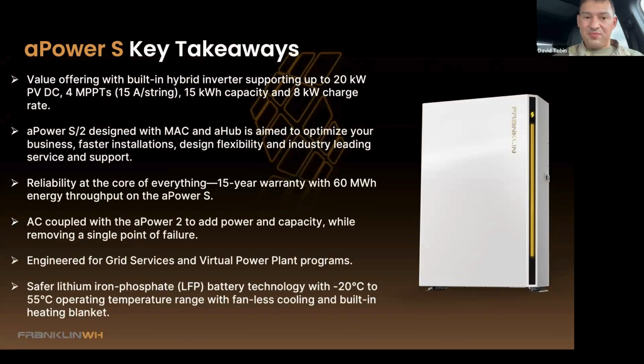The aPower S brings very good value by giving you 20 kilowatts of DC power. A question that may come up is that your charge rate is only 8 kilowatts while your AC output is 11.5 kilowatts, so yes, there is a bit of oversizing, but not a lot. When you're allowed to export to the grid and you're also near empty, you can utilize 8 kilowatts directly charging your batteries and 11.5 going out during that peak solar period. So you can actually utilize a lot of that power just from your solar system.